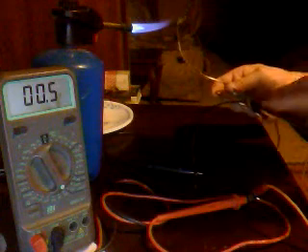If you come to a hot water tank or a furnace and it has a standing pilot, why pull the thermocouple all the way out and put it in a torch and hook up your meter to see what your millivolts are? When it's already in the pilot assembly, all you have to do is hold down the button and the pilot will stay lit. Pull the other end off the gas valve, alligator clip it, put it on millivolts — now it's in the standing pilot and you're able to test the millivolts.